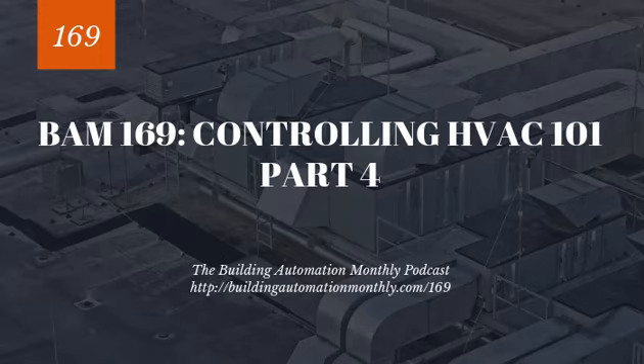And then finally, there's control. Now, when we control boilers, we're primarily focused on our boiler enable, our hot water pump command, any ISO valves if they are present, and our hot water supply set point. So boiler enable is pretty simple. Nine times out of ten, you're going to use a RIB U1C, and you're going to connect it to the outside of the boiler control module and wire it to the contacts on the control board.